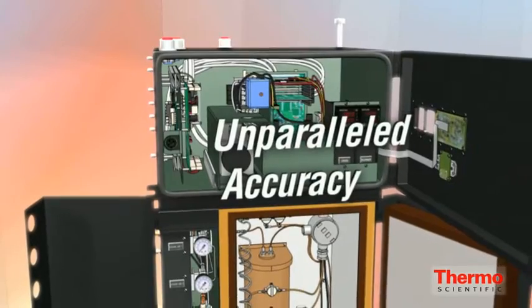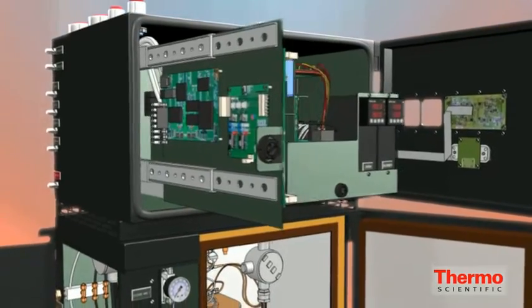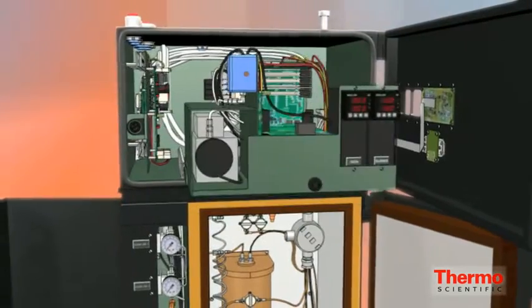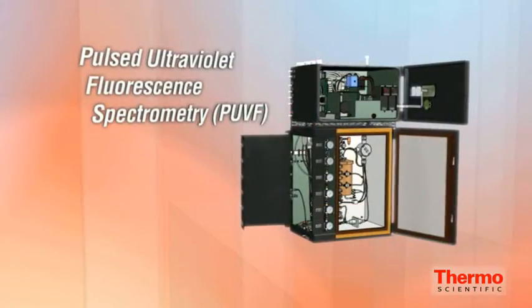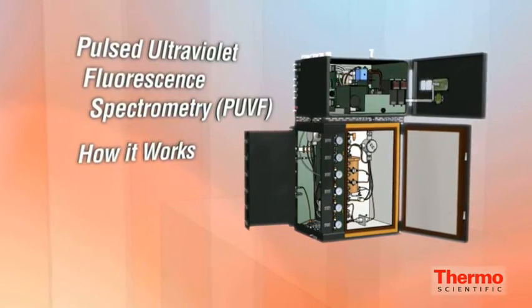The direction of sulfur concentration change is indicated in less than one minute. Preventive maintenance is required only once every six months. The SOLA-2 has a worldwide installation base and a strong track record for reliable operation. Superior analytical capabilities enable rapid determination of sulfur contamination sources.